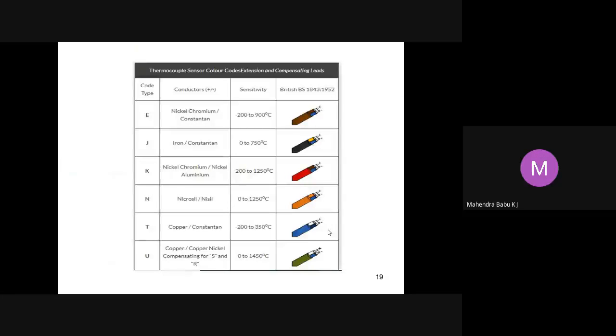This chart gives the thermocouple sensor color codes, extension and compensating leads. Depending upon the type of thermocouple, for example, a J type thermocouple means the material used is iron and constantan, its range is 0 to 750 degrees Celsius, and the color is black. Like this, we have different types of thermocouples with their colors and operating ranges.